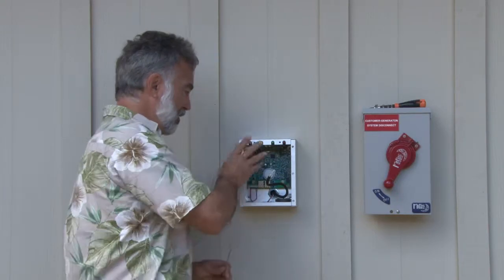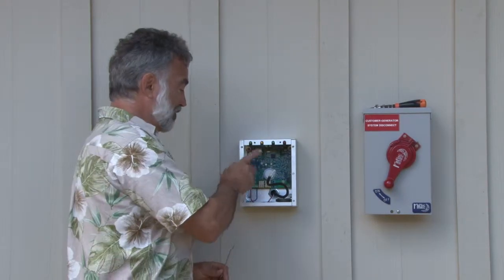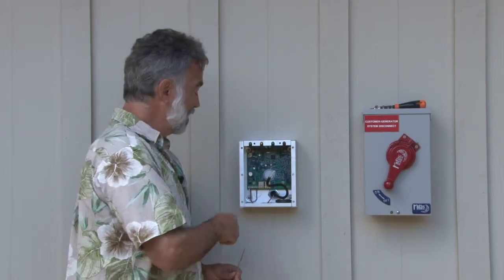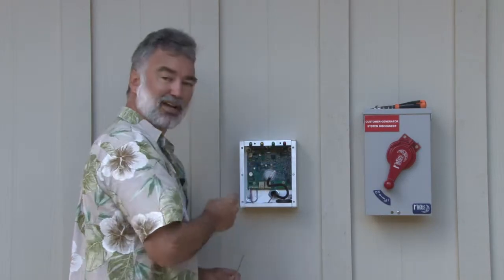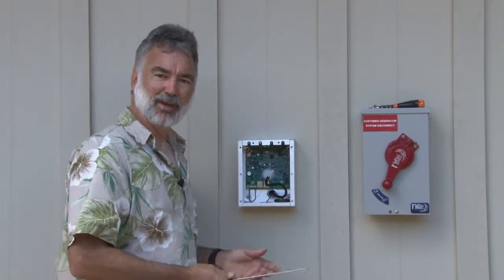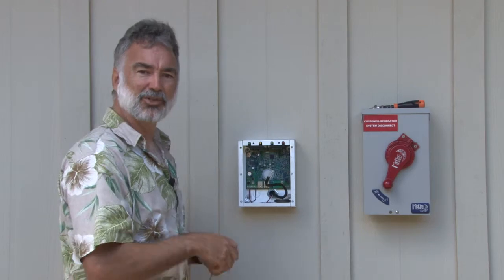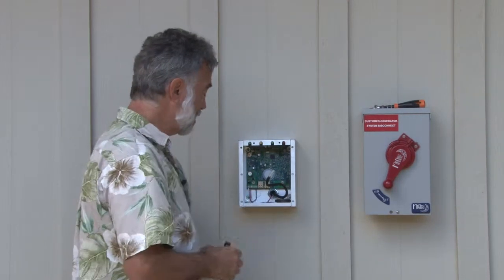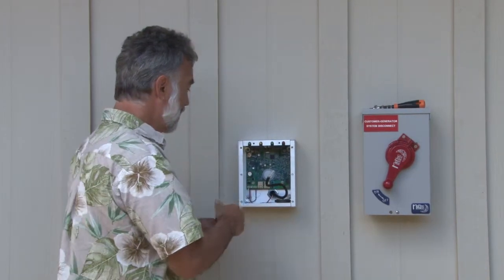In order to make this safe, you turn off the power to the PV system by hitting this button. The battery backup takes over and turns it off. The battery is good for 24 or more hours with no solar and no AC power supply connected, so you're pretty good there.